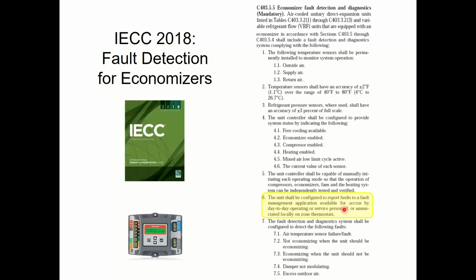Now, most thermostats don't do that. That's a special thermostat. And that's why there was only like 7 models of thermostat that comply with everything for code in our states. Because to do all the things we have to do with the set points and the setback and the occupancy interconnection to the damper, and now this fault management report going to the thermostat, only certain thermostats can do that. Like I said, there's a Venstar model number. Actually, there's 2 Carrier model numbers now. No, there's one. There's 2.